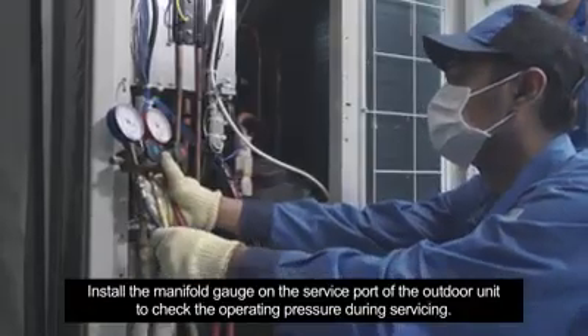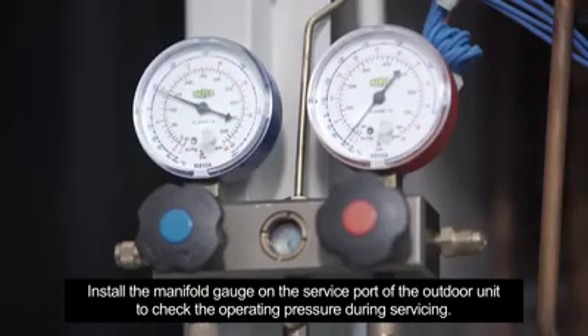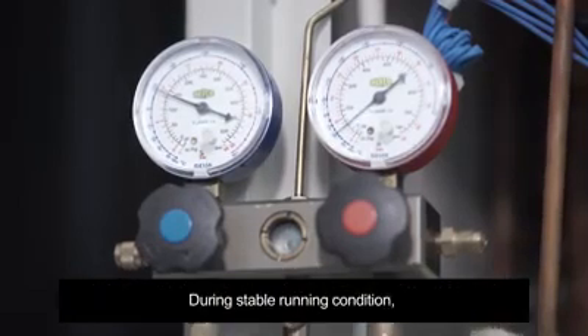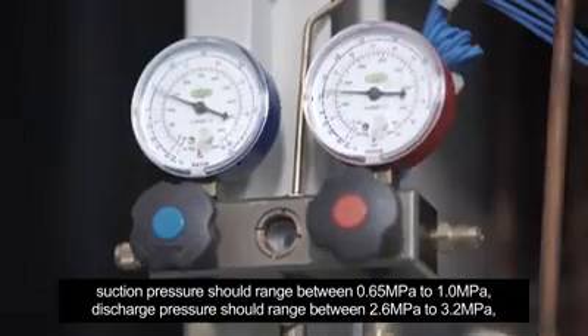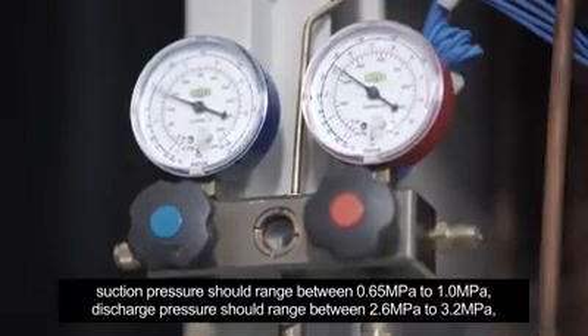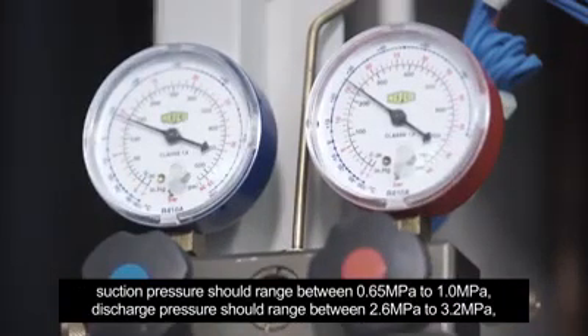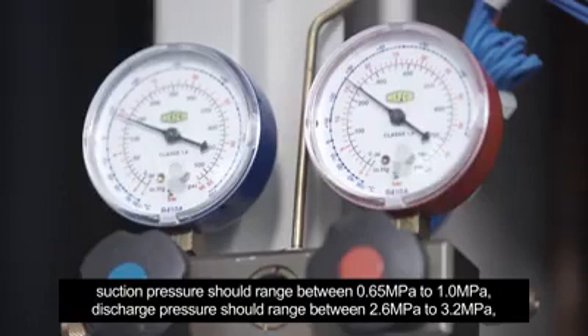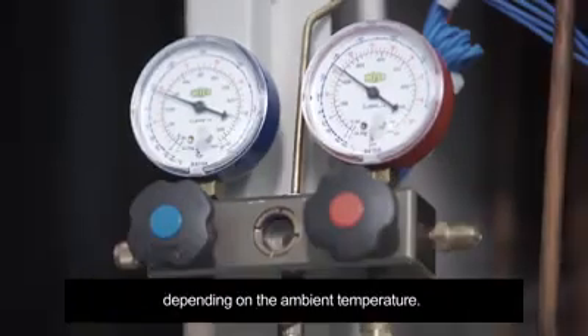Install the manifold gauge on the service port on the outdoor unit to check the operating pressure during servicing. During stable running condition, suction pressure should range between 0.65 megapascal to 1 megapascal. Discharge pressure should range between 2.6 megapascal to 3.2 megapascal, depending on the ambient temperature.